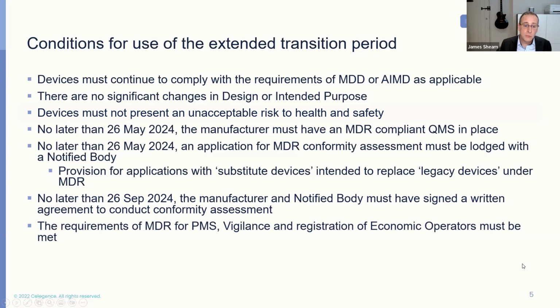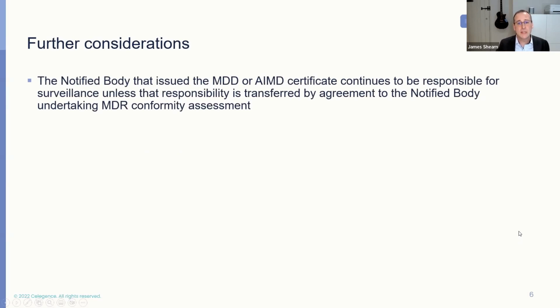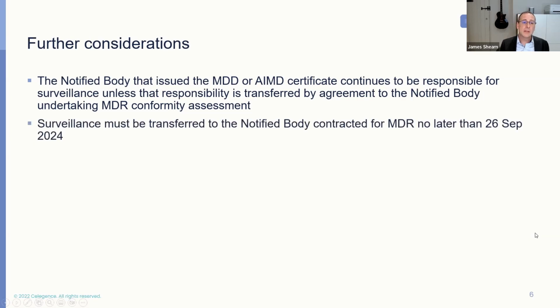There is still the ongoing requirement for post-market surveillance, vigilance, and registration of economic operators to be carried out to the requirements of MDR during this period of time. So what are the further considerations around this? The notified body that issued the MDD or AIMD certificate continues to be responsible for the surveillance of that device unless that responsibility is transferred by agreement to the notified body undertaking the MDR conformity assessment. And that surveillance must be transferred to the notified body contracted for MDR assessment no later than the 26th of September 2024.